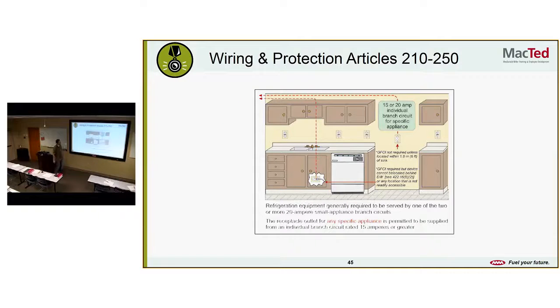What do we got here? So refrigeration equipment is generally required to be served by one of the 2 or more 20 amp small appliance branch circuits.